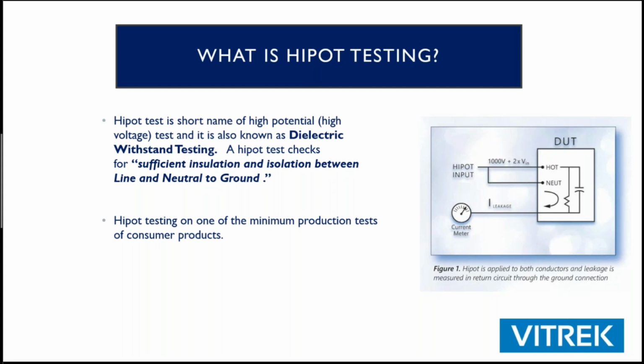So typically what you're going to do in a HIPOT test is you're going to hit it with significantly more voltage than it's going to see during regular use. Roughly 10 times. It's usually 2 times the voltage plus 1,000. And you're going to make sure that a breakdown doesn't occur or there isn't an excessive amount of leakage current. And this can be applied all over the place, from a cable or harness, a subassembly, a printed circuit board, or in this case, a finished product.